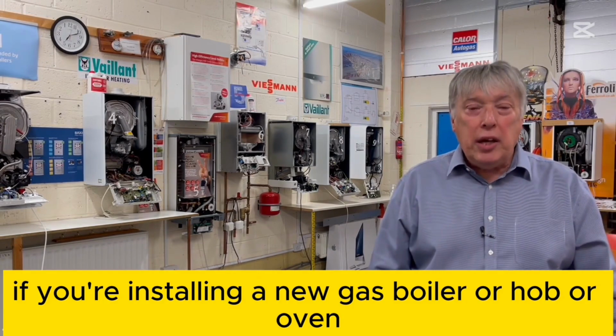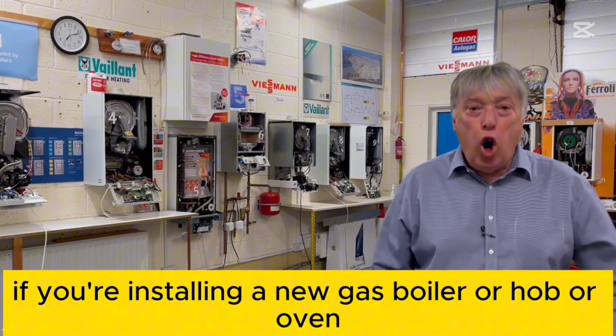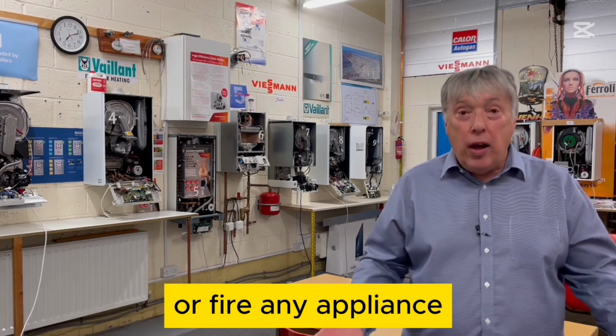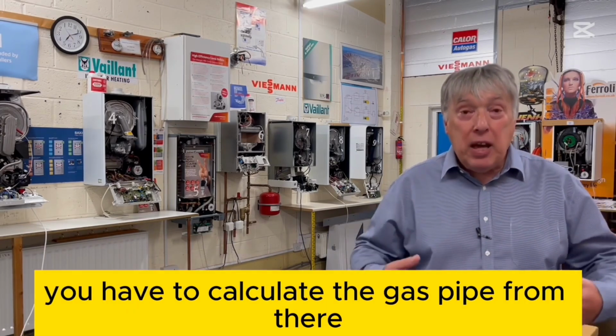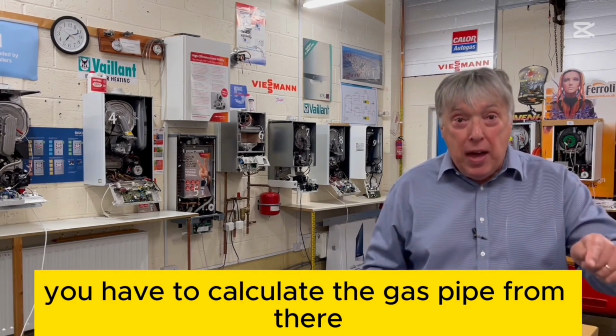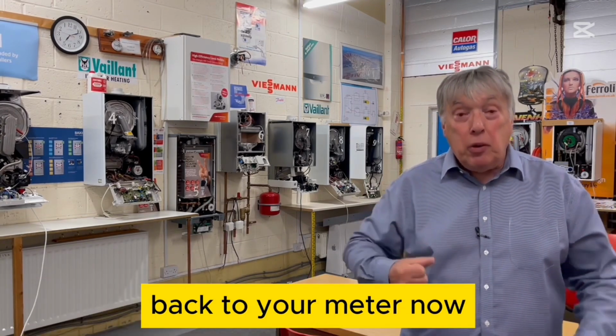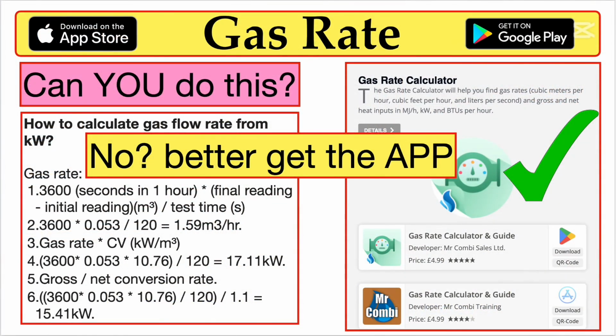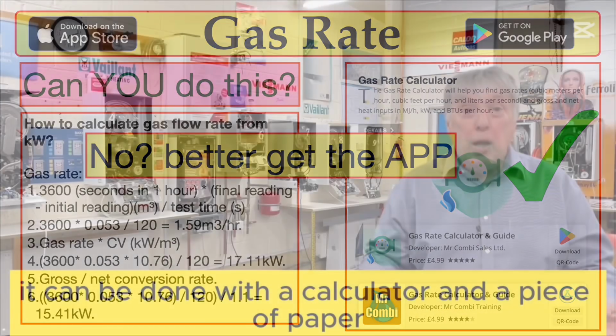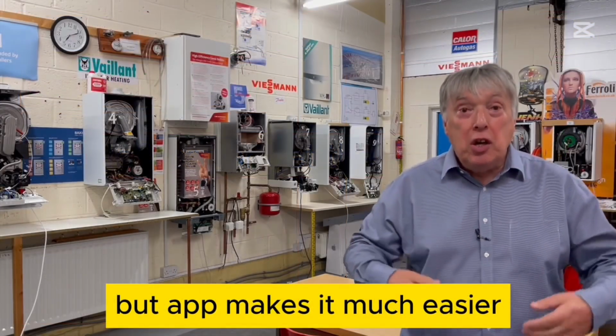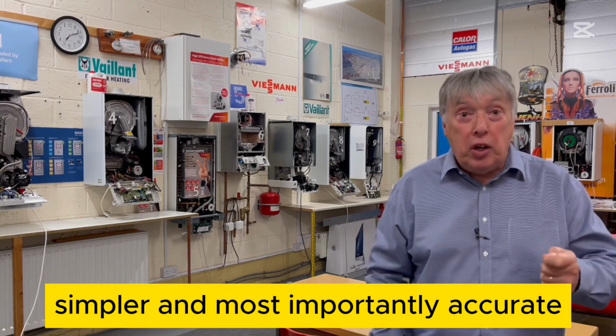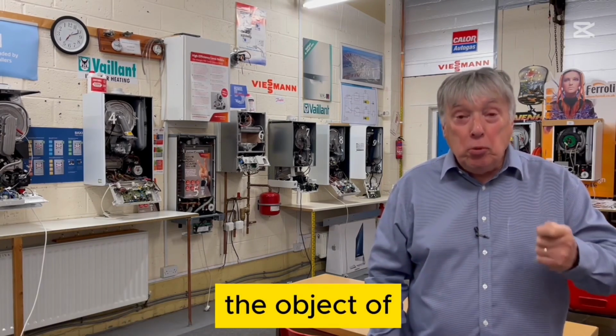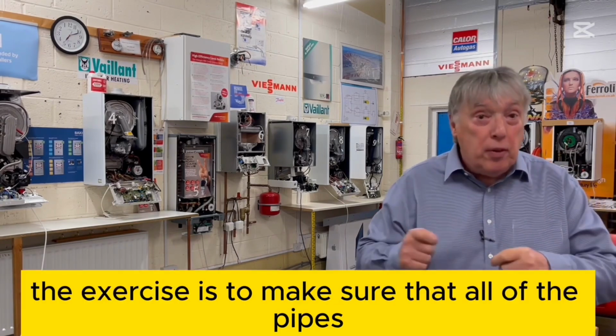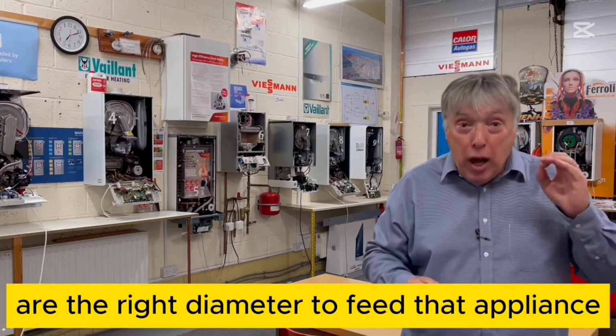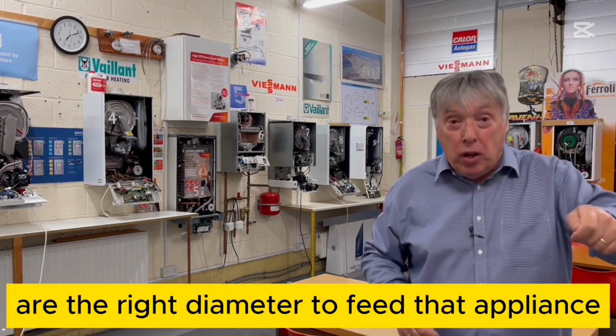If you're installing a new gas boiler or hob or oven or fire, any appliance, you have to calculate the gas pipe from there back to your meter. Now it can be done with a calculator and a piece of paper, but our app makes it much easier, simpler, and most importantly, accurate. The object of the exercise is to make sure that all of the pipes around the house are the right diameter to feed that appliance.